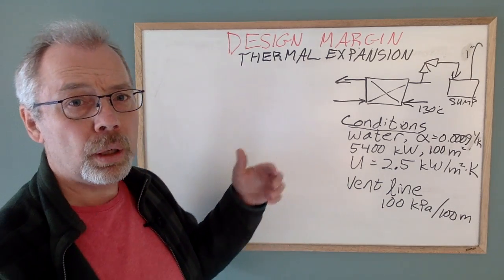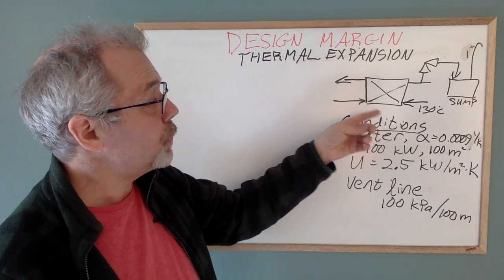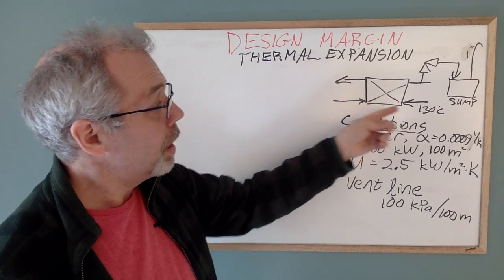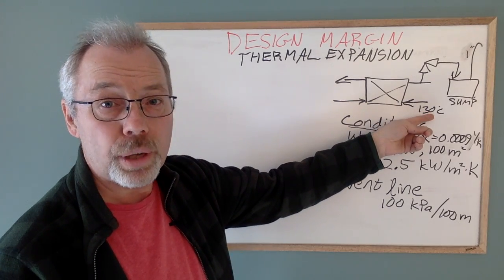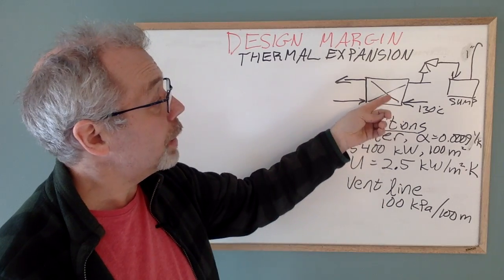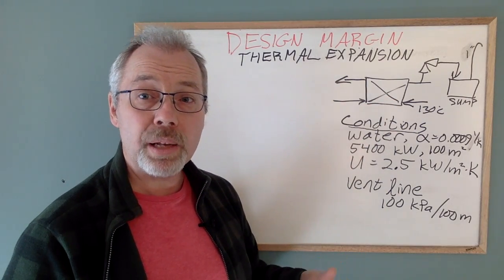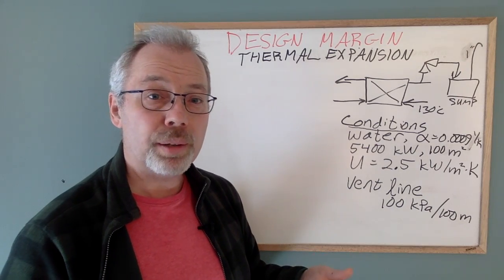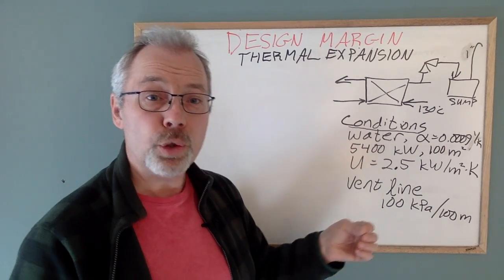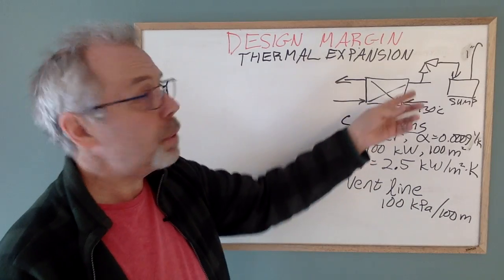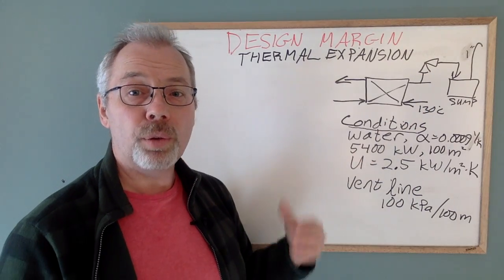Now, with our exchanger, we will imagine that the cold side is blocked in, and we start the hot side flow. The cold side warms up a little bit, the cold side fluid expands, and since the cold side is blocked in, we can rupture the exchanger. And that's why we put a small PSV on the cold side.